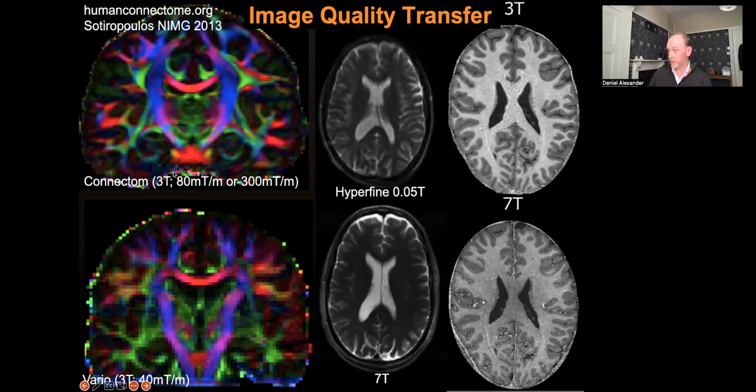So although the field strength is about the same, the ability to make a gradient in that field strength is much stronger than usual. And that is important, particularly for certain imaging modalities, in particular diffusion imaging, which I mentioned earlier is a critical component of these microstructure imaging techniques. That is a substantially enhanced capability.